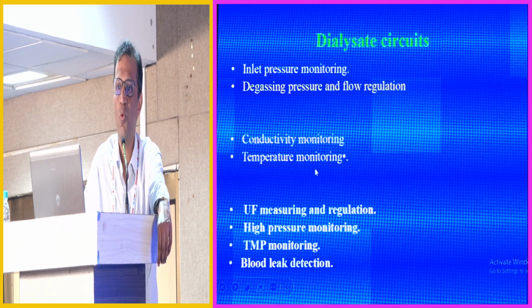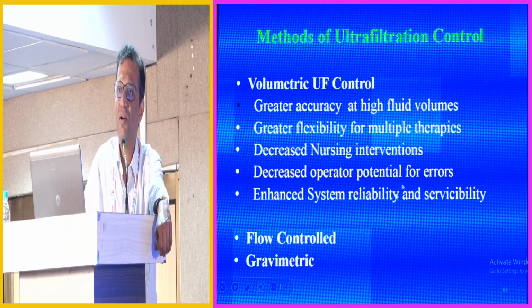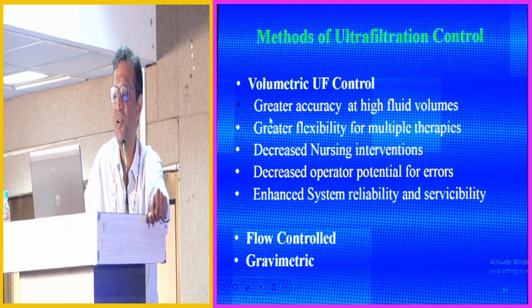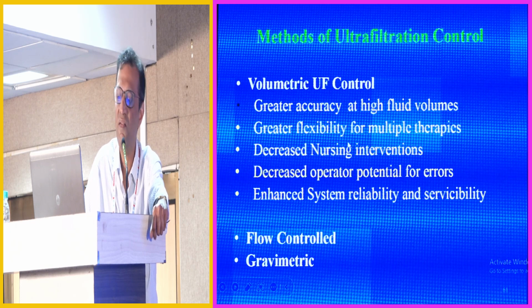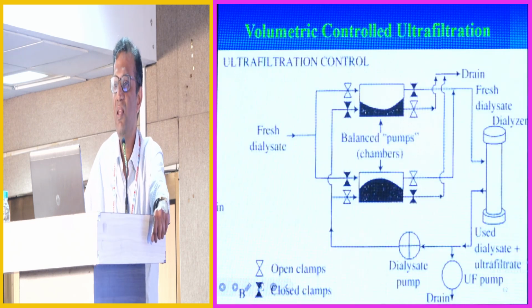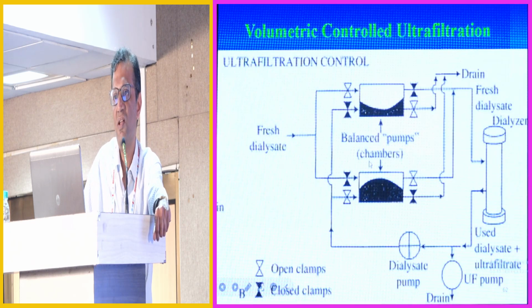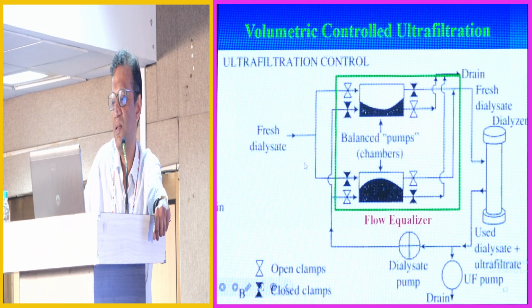Finally, we have to do ultrafiltration. The most common system for doing ultrafiltration today is the volumetric system, a balancing chamber. In the Gambro AK series, there is flow control, and as we saw from most of this morning, the CRRT machines have a gravimetric control. In the balancing system, we have a fresh dialysate which must be balanced by an equal volume of spent dialysate.